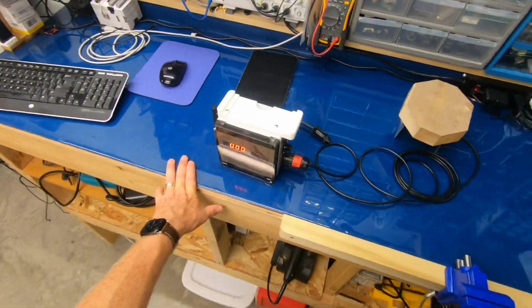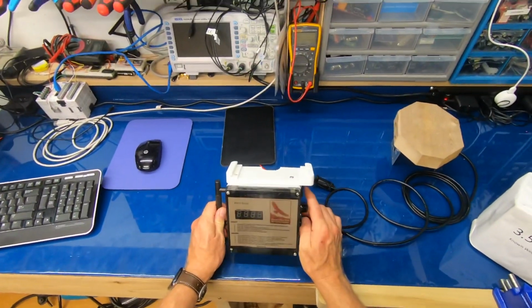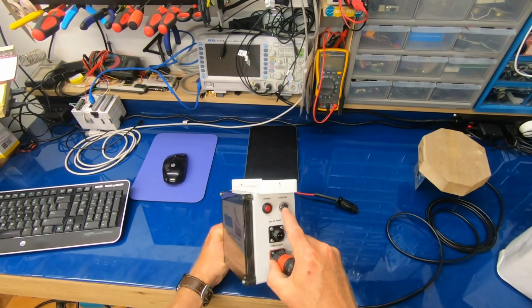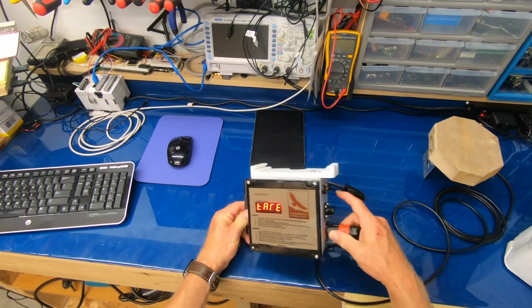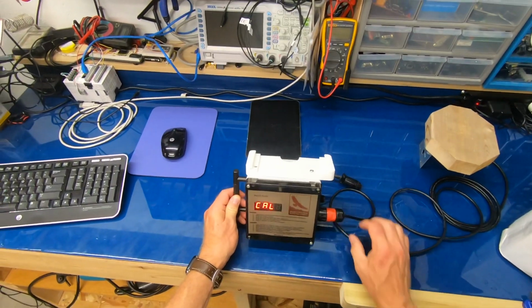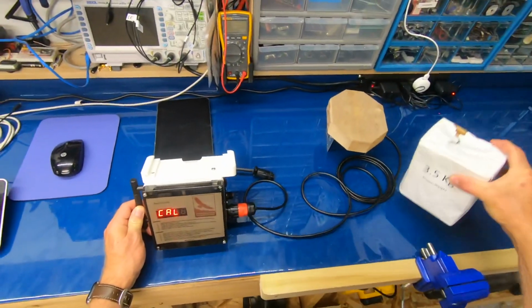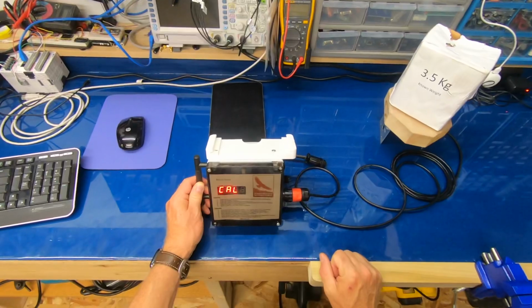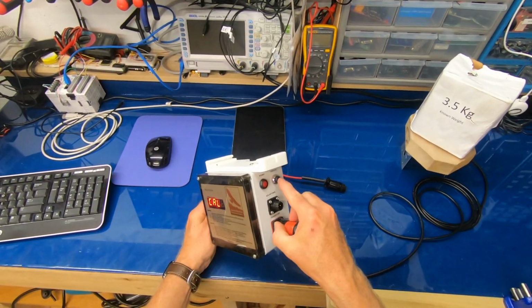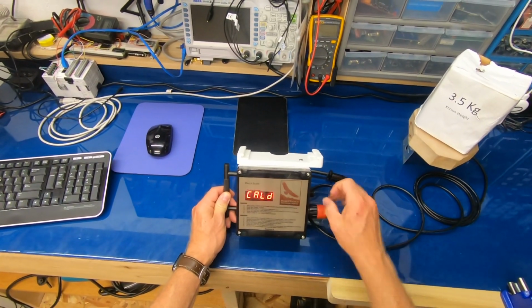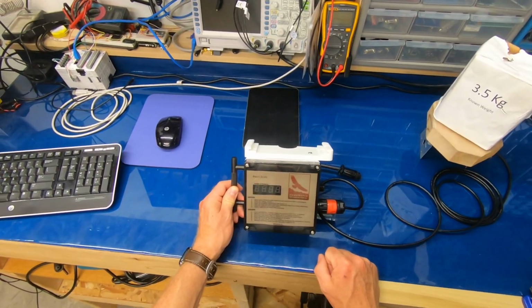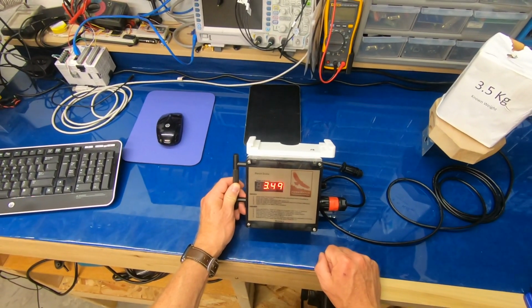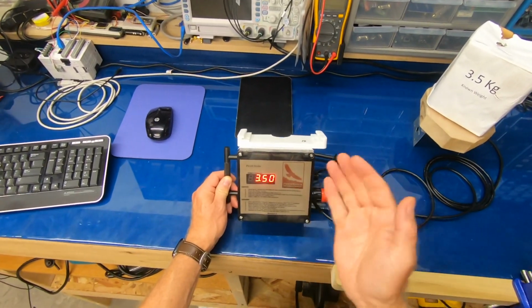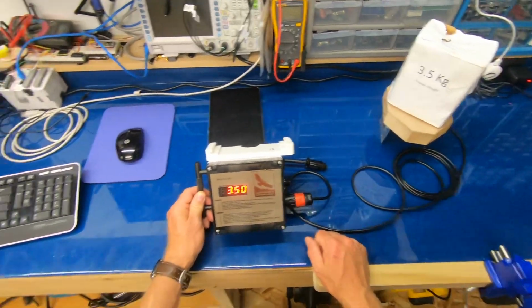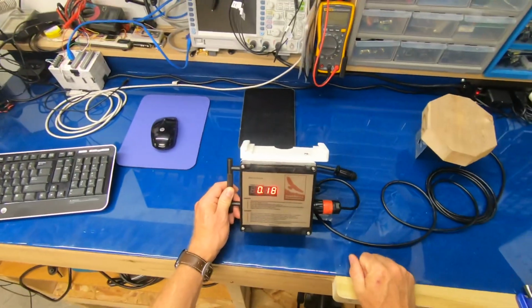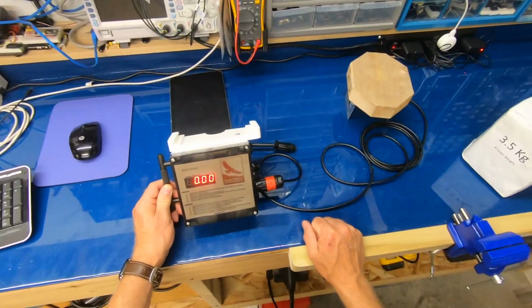As last year, you'll have to calibrate each of them when you get them. To do that, you're going to press the tare cal button for 3 seconds. After 3 seconds, it'll show tare. It's going to re-tare. And then it's going to show cal. You'll place the known weight on there of 3.5 kilograms. Once you're done with that, you'll press the tare cal button again. It'll display calibrated, or CALD for short. Once it's done, it'll start to measure weight, and it should show the 3.5 kilograms, which it did. And now you're calibrated, ready to roll. Take the known weight off, and the scale is ready for use.